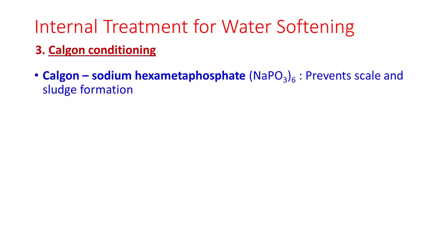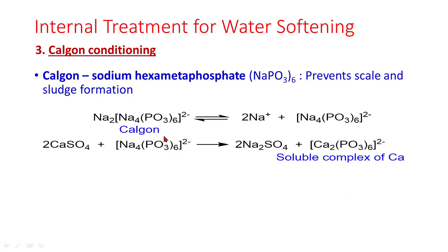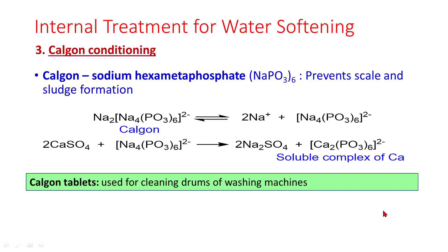Calgon conditioning: Calgon is sodium hexametaphosphate, (NaPO₃)₆. It prevents scale and sludge formation. Calgon dissociates to give Na₄(PO₃)₆²⁻, which is a complex ion. It reacts with permanent hardness to give rise to a soluble complex of calcium. Calgon tablets are also used for cleaning drums of washing machines.